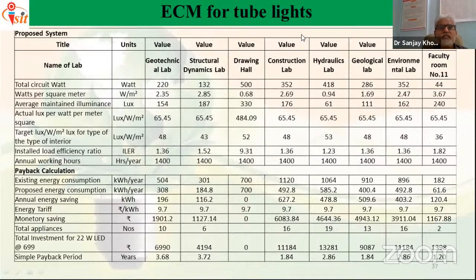Now, energy conservation measures for the tube lights, for the geotechnical labs we'll see. This total target ILR is now 1.36. Annual working hours are considered as 1400, based on the usage of that particular building—whether daily usage is 6 hours or 10 hours depends on the type of application. Here it's considered as 1400 hours per year based on discussion. So existing energy consumption, considering 1400 hours, comes to 504 electric units per year.